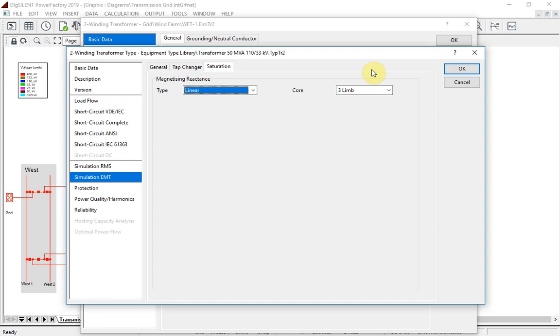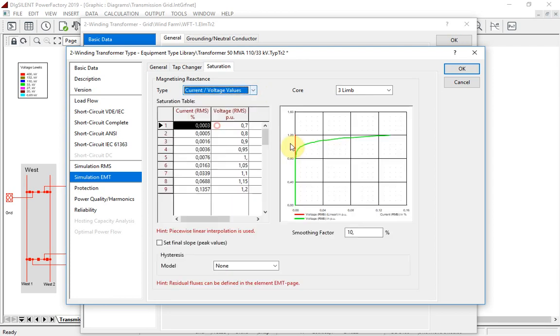Furthermore, the saturation curve can now be defined in PowerFactory, based on RMS current and voltage measurements, which are frequently provided by the manufacturer. The measurements of the voltage-current relationship are usually only executed up to a voltage of 1.2 per unit.